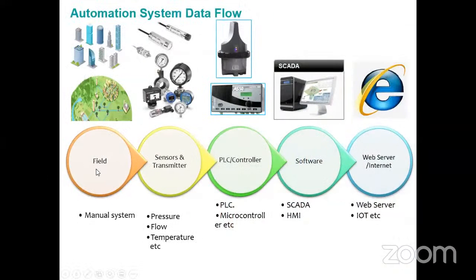So here the data starts from the field - I write manual systems. Field can be anything: if you see the building, it can be your room temperature, or humidity, or current voltage, anything. Or if you are working in a pipeline or in the water sector, water flow can also be the field for you. So sensors take the data from the field, convert it to another energy, and the transmitter converts it to the proper signal that can be read by the PLC or the controller.